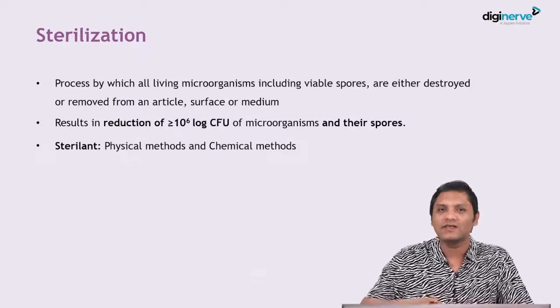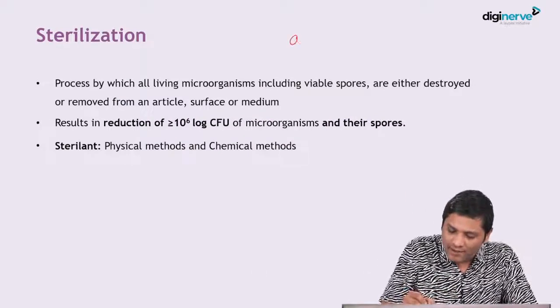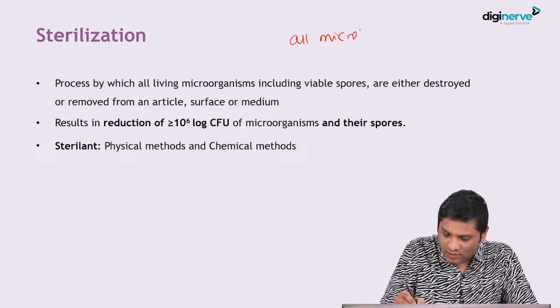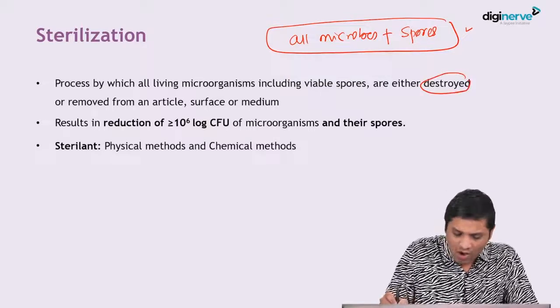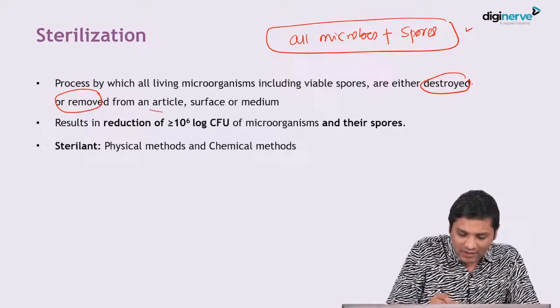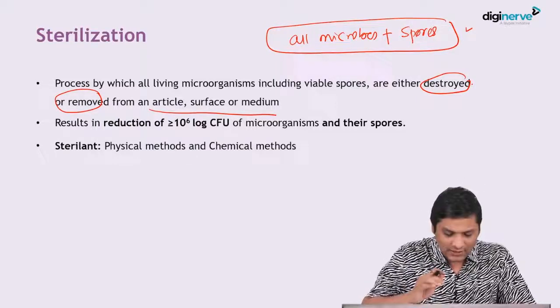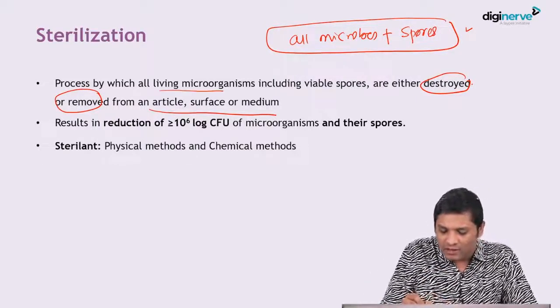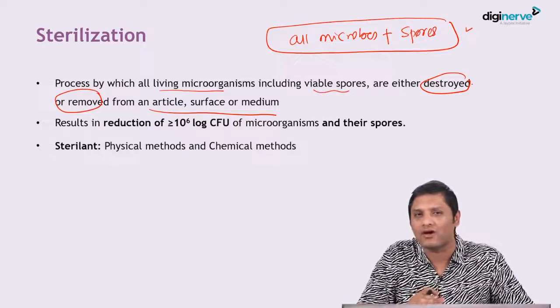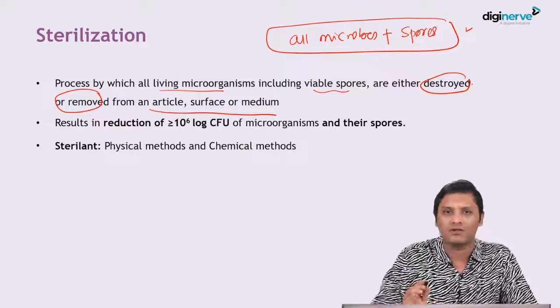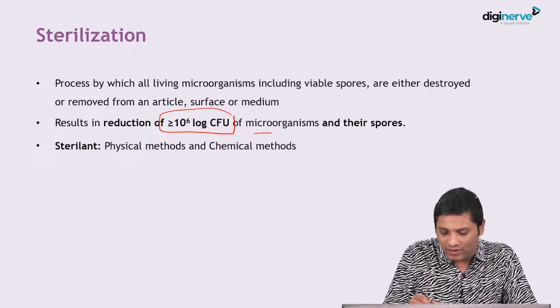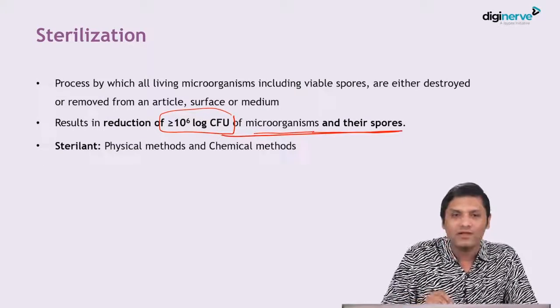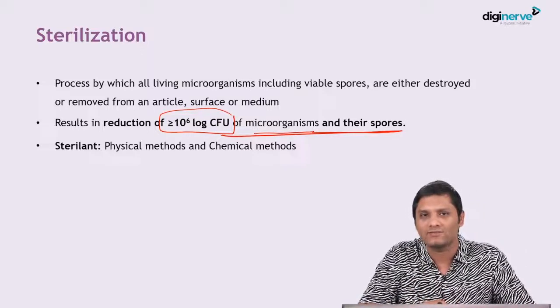First is sterilization. Sterilization is a process by which all microorganisms and their spores — including bacterial spores — are either destroyed or removed from an article, surface, or medium. You will have a log reduction of 10 to the power of 6 colony forming units; microorganisms and their spores will be reduced by the process of sterilization.